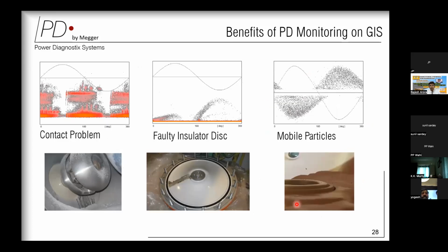Let's see some of the errors which are captured and the effects which are seen with PRPD pattern. So first we can see is the contact problem. Whenever this kind of problems were captured, we see the corresponding PRPD patterns, and when the GIS was opened, we could see what kind of problems we could face with this kind of particular pattern. So we have captured those data and segregated them, so it is quite easy for any user to understand the cause and analysis. If there is a PRPD of this nature, it indicates there is a contact problem, and this is something which you can see visibly when you open the GIS.